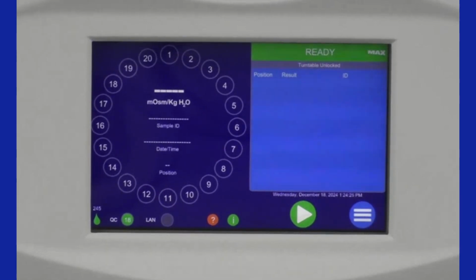First, I'm going to start with the home screen to show you everything that's happening here, all the different indicators, and where you can expect to see certain information pop up. Taking a look at the screen all the way over to the left, you'll see a little green teardrop looking thing with a number above it. That's the Max 500 counter I was talking to you about before. After you have performed your 500 test maintenance, that number will reset up to 500. Then each test you run will count 1 off of that 500 number until it counts all the way back down to 0 again. That little green teardrop indicator will change to yellow and then to red as you work through the process.